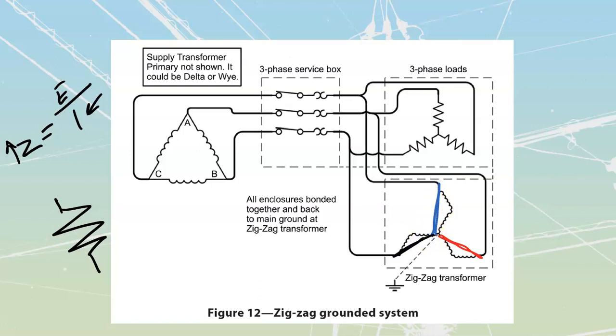If I were to go and do that, there would be an issue where this is going to be a line-to-line value of voltage delivered back across the line-to-line value of voltage over here. Remember how the zigzag transformer cancels out its flux? This wouldn't do any flux cancellation, so we're going to have a large amount of current that gets dropped across from one to the other.